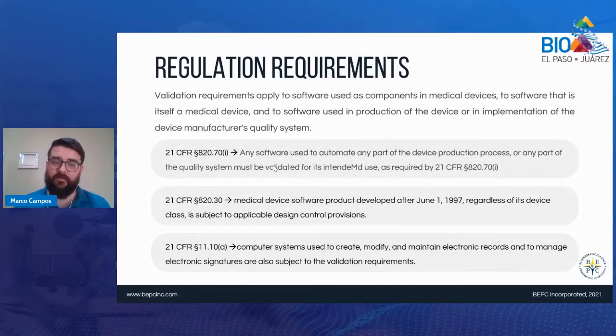Or the implementation in the device manufacturer's quality system. So when you talk quality system, PMs come into play, calibrations come into play, training comes into play, which is one of the use cases mentioned. So not only if you're going to be looking at doing something specifically for the medical device itself, but are you going to be doing anything that encompasses that medical device world or the quality system, you have to think about the regulations. There's several regulations applicable to this, but in a nutshell, 21 CFR 820 is really where the medical device regulations from FDA is located. And then there's different chapters where you can go look for more details. But essentially...